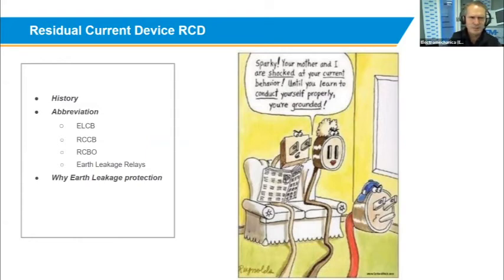Now we get to the RCDs, the residual current devices. Again, there are a lot of abbreviations, and one does get confused about what is an ELCB, what is an RCCB, what is an RCBO, when do I use earth leakage relays, and so why must we have earth leakage protection? I mean, if the installation is done properly according to regulations, there are not supposed to be any live wires. If the wiring accessories in your house, the plug sockets, are working, you're not supposed to be able to put something in there that can actually electrocute you. So why then use earth leakage protection?